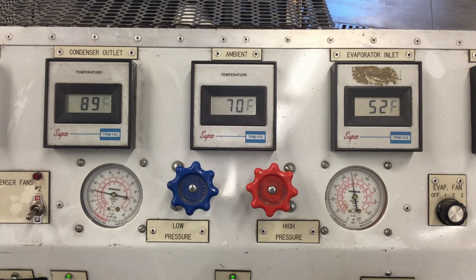The air conditioning has stabilized pretty well. Just by controlling the cooling fans we were able to stabilize the cycling. Obviously if it gets above 250 PSI on the high side, we'd want to kick on the high-speed fans at some point.